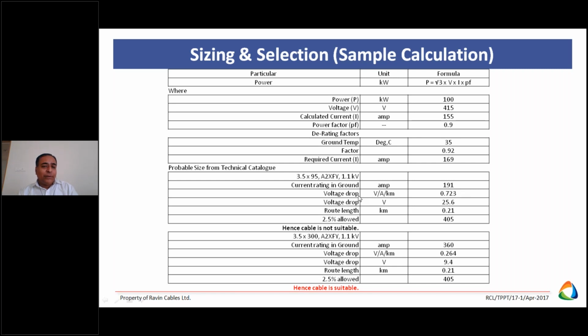Now voltage drop, as per the resistance, we calculate the voltage drop for route length 210 meters. Voltage drop is 25.6. It comes 405. Maximum allowed is 405. 415 minus 25 is less than 405, so this cable is not suitable. Now go for the next higher size, maybe use copper. This is hit and trial. Just put values in the Excel sheet and you get the required size of the cable conductor. So this is just sizing and selection of the cable.